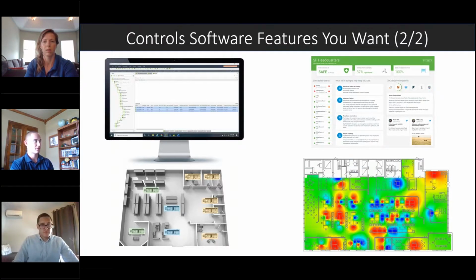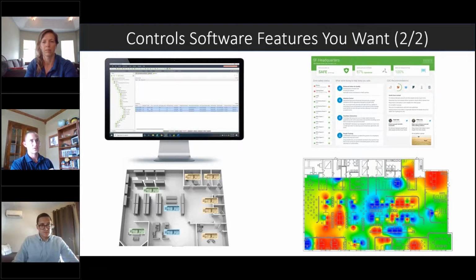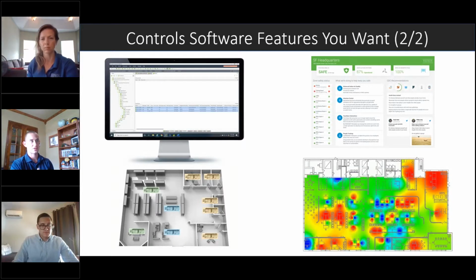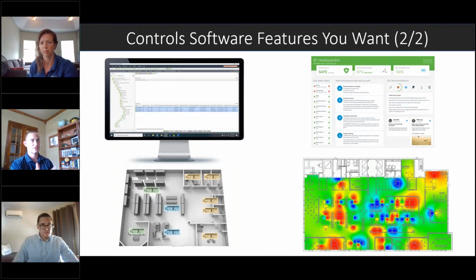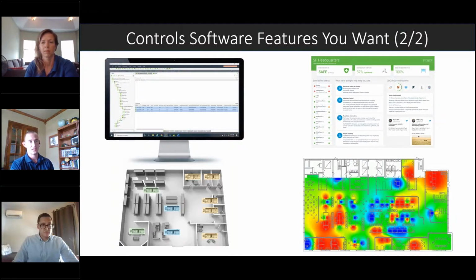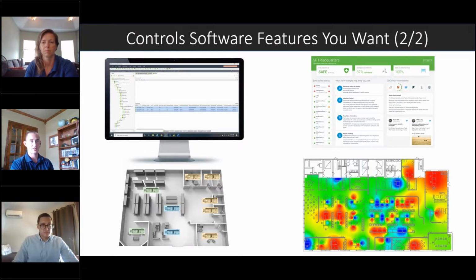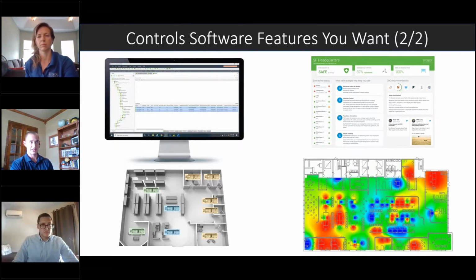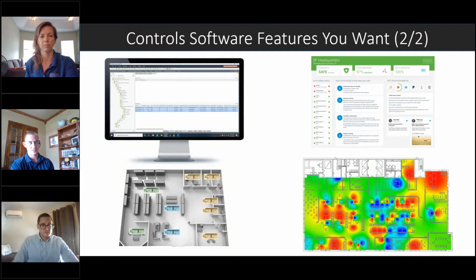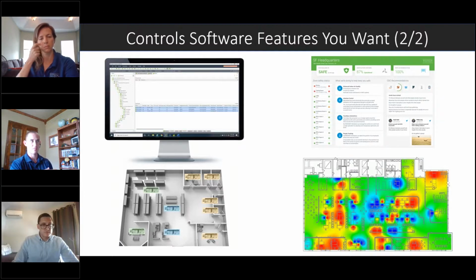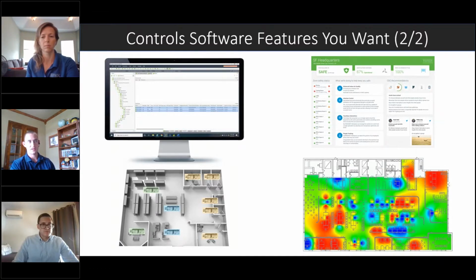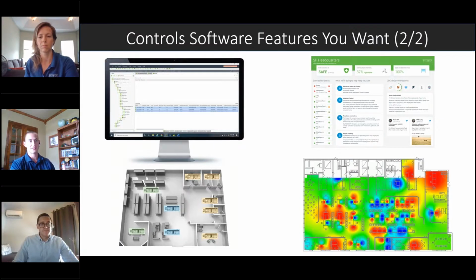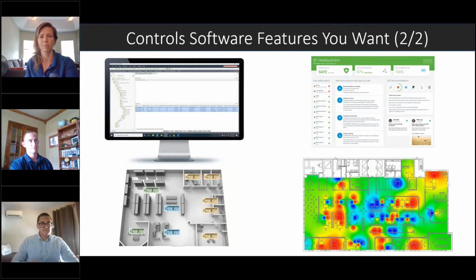And the really nice part about it is it's set up so that you can run it on a live system without tripping any alarms. So you could set this up and have it run every Friday, the commissioning report, or once a month it goes there and runs that commissioning report. And when it gets done, it'll automatically email you. If you set it up to do so, you can have it automatically email the report to you, and it'll say which VAVs passed and what tests they passed and which tests they failed.